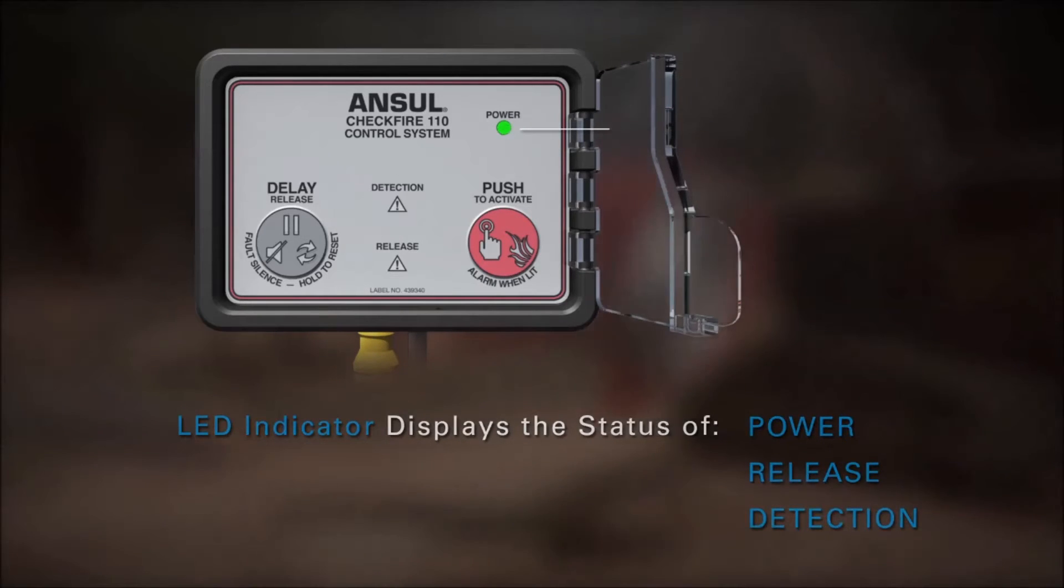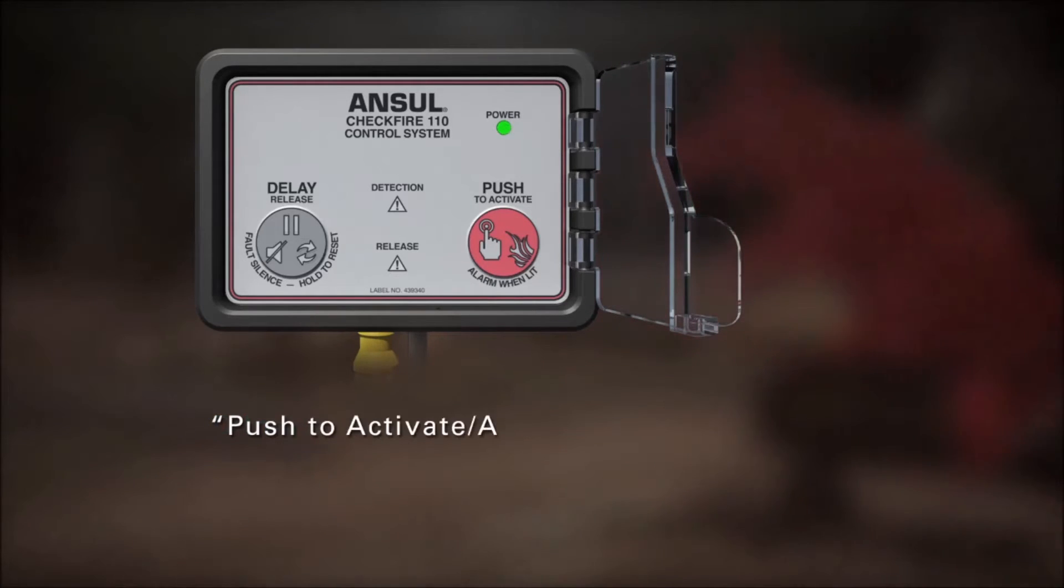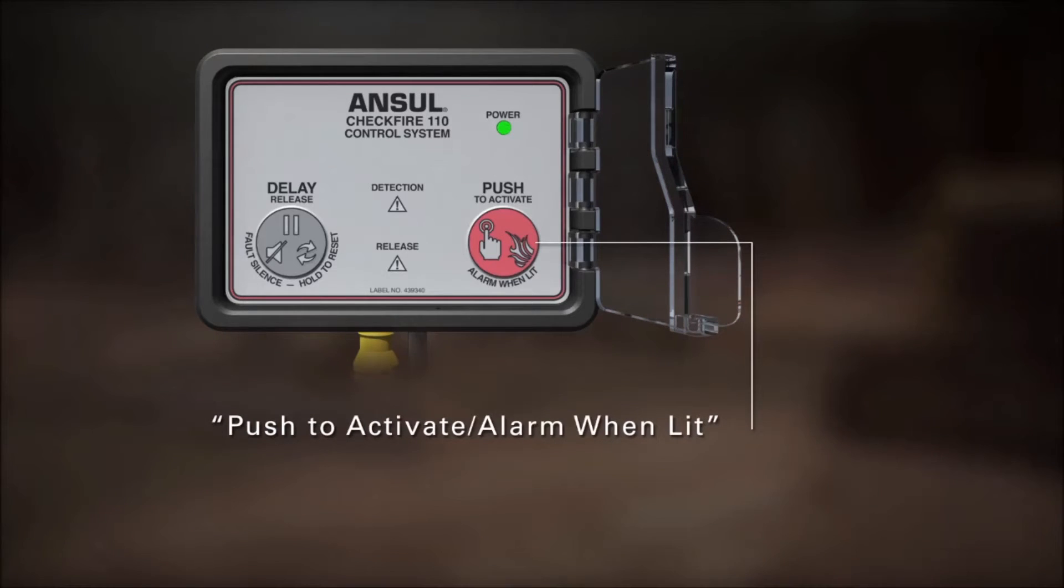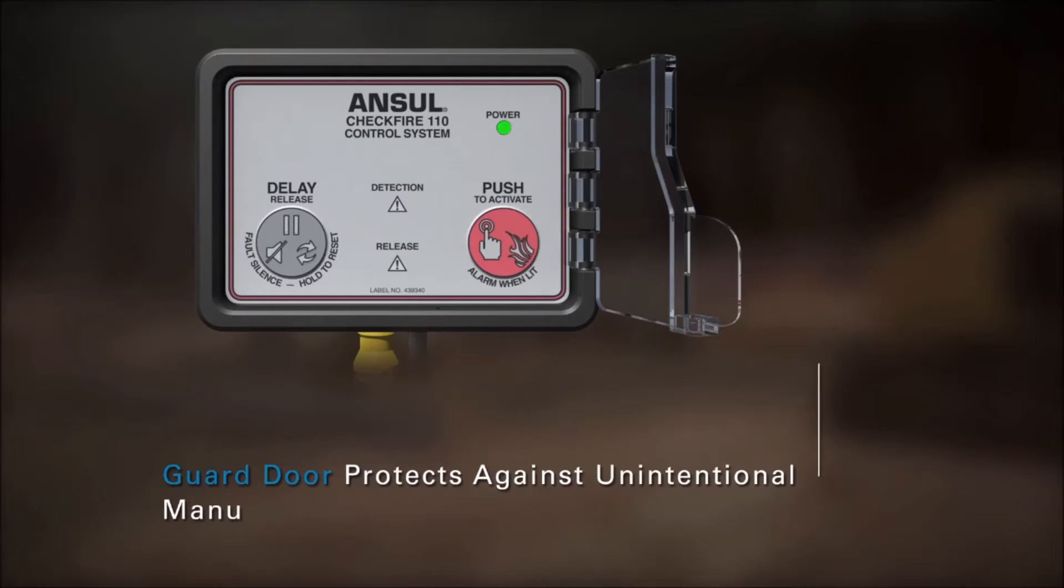The system can be electronically actuated using the guarded manual activation button. Pushing the button immediately triggers the release circuit and illuminates the red LED for 10 seconds.